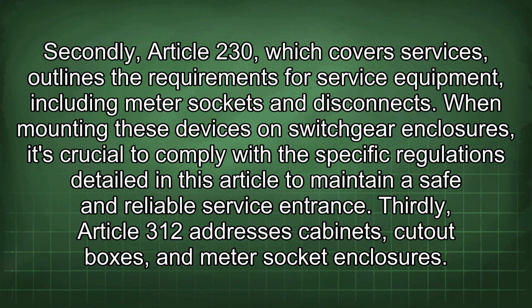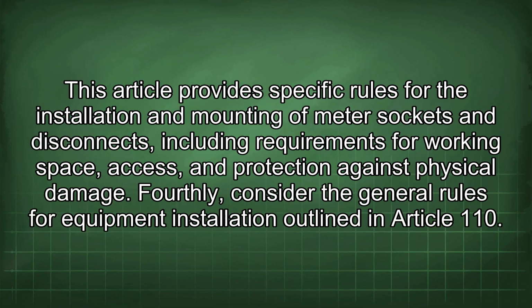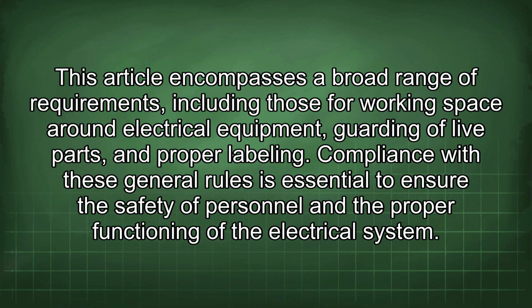Thirdly, Article 312 addresses cabinets, cutout boxes, and meter socket enclosures. This article provides specific rules for the installation and mounting of meter sockets and disconnects, including requirements for working space, access, and protection against physical damage. Fourthly, consider the general rules for equipment installation outlined in Article 110. This article encompasses a broad range of requirements, including those for working space around electrical equipment, guarding of live parts, and proper labeling.